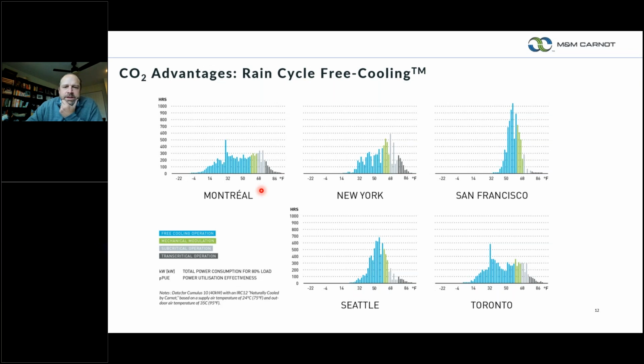I just wanted to show the amount of economizer hours that you can get in different areas of the country. It's related to the climate in whatever zone you're installing this equipment, but we also allow you to use adiabatic gas coolers to help in warmer climates, where we can maximize the free cooling hours. The other colored lines here are the different modes of operation that you would have with a transcritical CO2 system. I wasn't planning on getting into the technical details, but basically you have transcritical cooling and then subcritical cooling, and subcritical cooling happens when you get below the critical point of CO2. That green line is where we have mechanical cooling, but we're modulating the compressors to save energy until we can get to the point where we can lock out the compressors and do free cooling with the system.